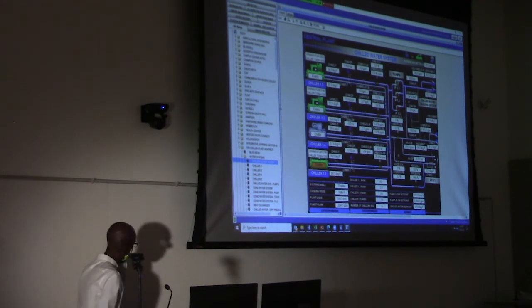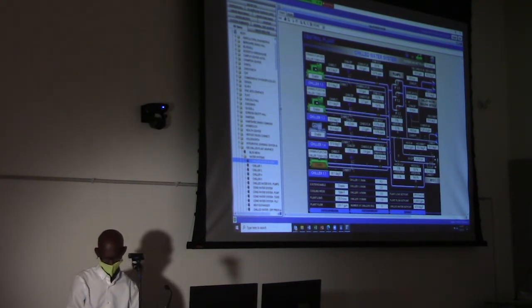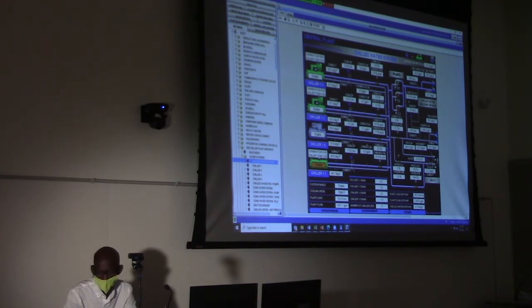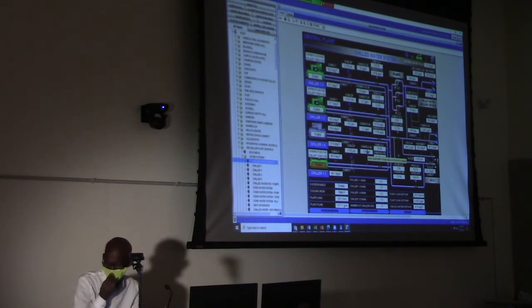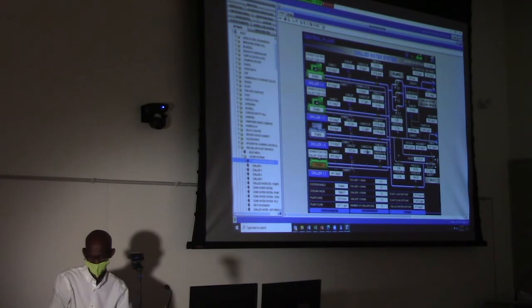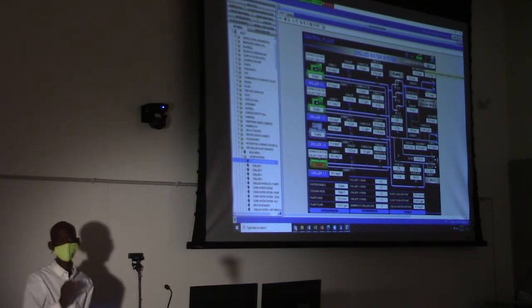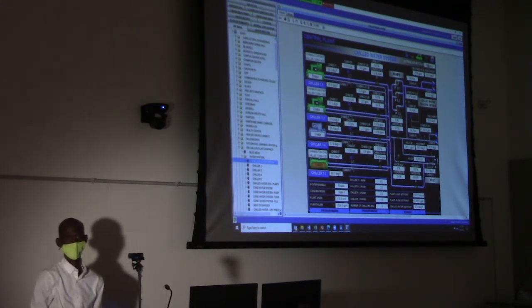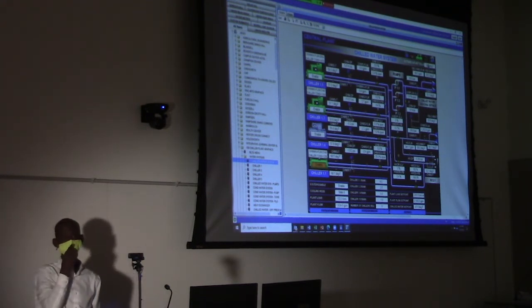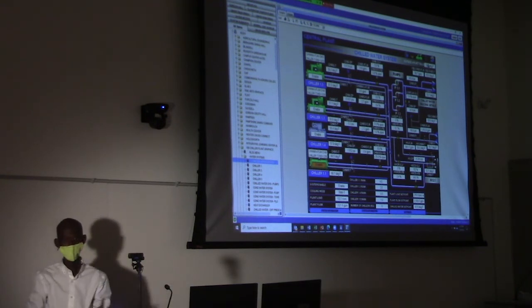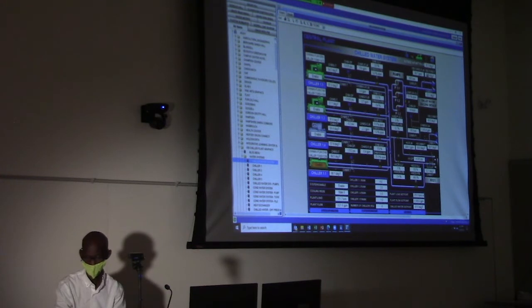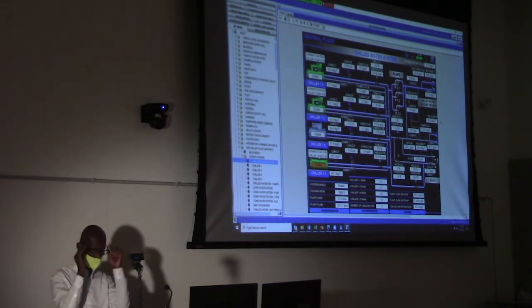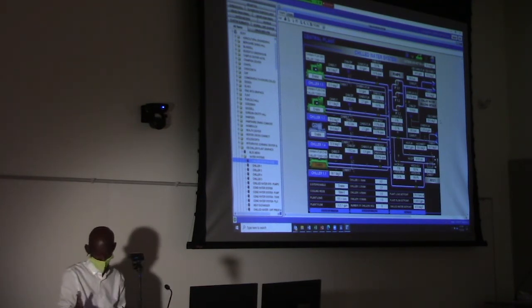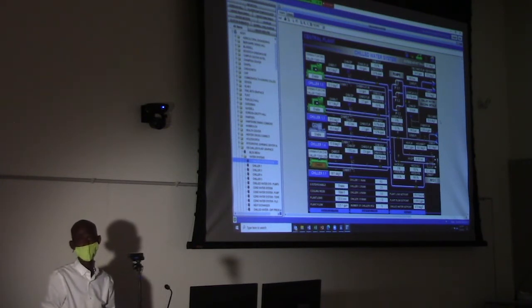So here I can see how many chillers we have running. The chillers tell you which one is enabled, but it tells you also which one is on, based on the flow. So here based on the flow, I don't have any running. But I'm not worried too much. Why is that? It's because my temperature outside is 28 degrees wet bulb. So you don't need to run a chiller where you can have free cooling. So what we do is circulate water to the cooling towers. The cooling towers cool that water, we bring it back, we give it to the labs, and our supplied chilled water here is 55 degrees, and you have it returning at 58 degrees. Perfect. So those are the features of a building automation system. And it's done automatically based on outside air temperature.